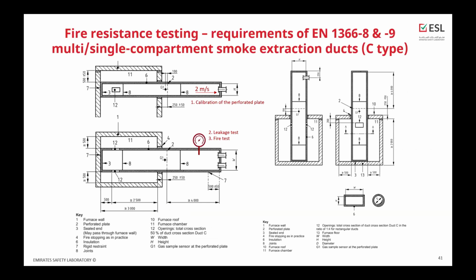So why is there a 2 meters per second criteria? Because this 2 meters per second is related to the perforated plate. First, we need to calibrate the perforated plate as a laboratory. If this is correct, you as a manufacturer are fixing this plate within your duct, and then we are doing the leakage test. After the leakage test has a positive result, we are proceeding with the fire testing.